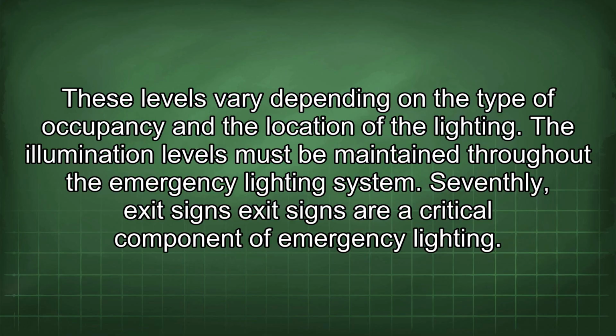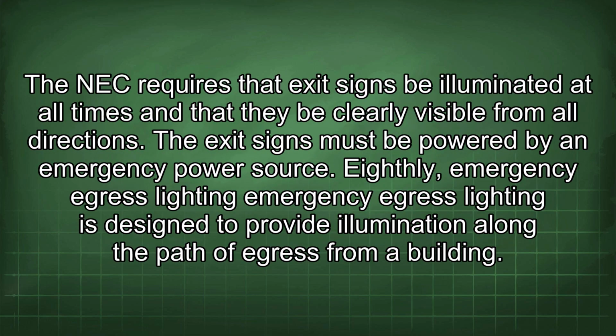Seventhly, exit signs. Exit signs are a critical component of emergency lighting. The NEC requires that exit signs be illuminated at all times and that they be clearly visible from all directions. The exit signs must be powered by an emergency power source.